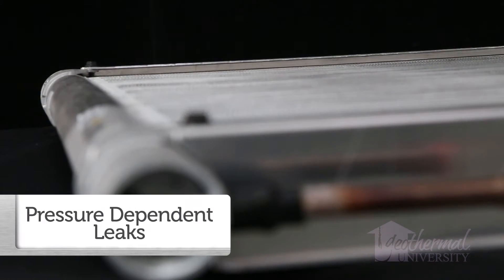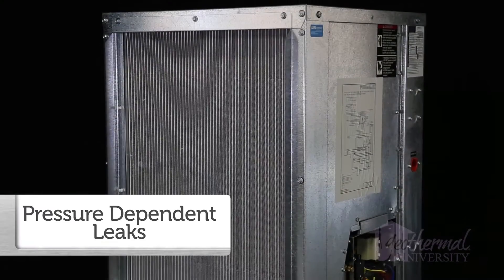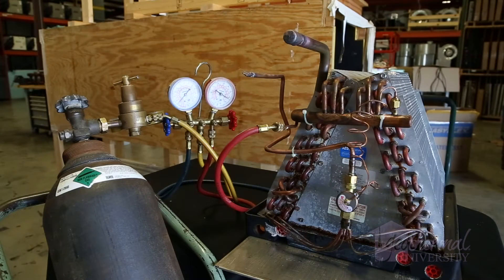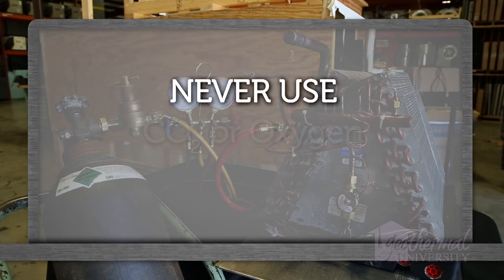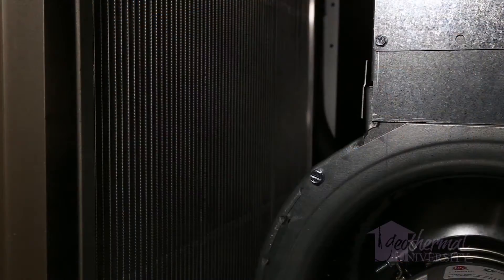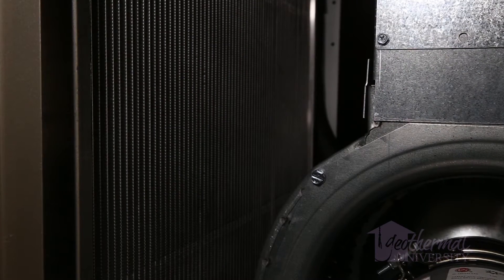There's pressure dependent leaks which are leaks that can only be detected as the pressure is built. Nitrogen is used to pressurize a system up to 400 psi. Never use CO2 or oxygen. Helium will also work. Pressure dependent leak testing should be conducted if no leaks are discovered by the standing test.